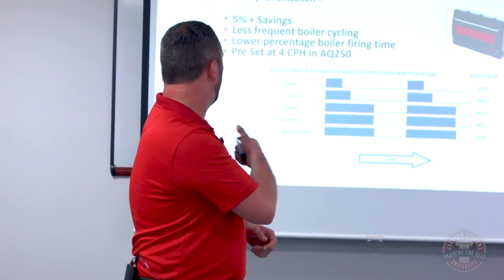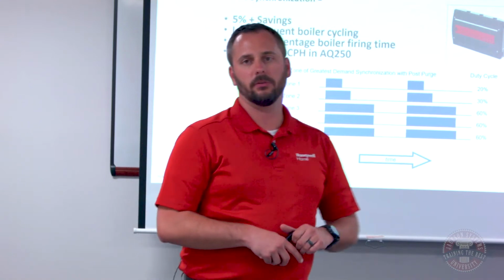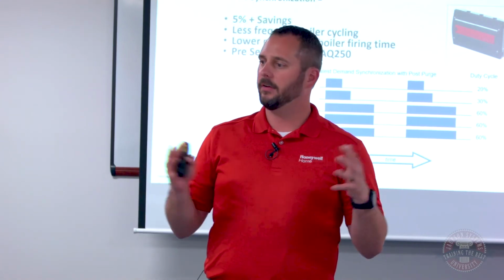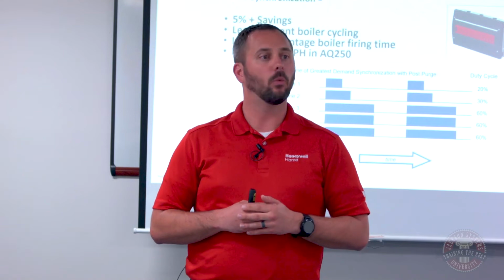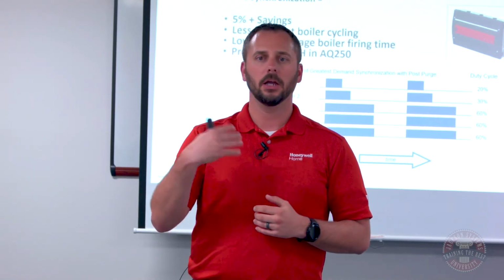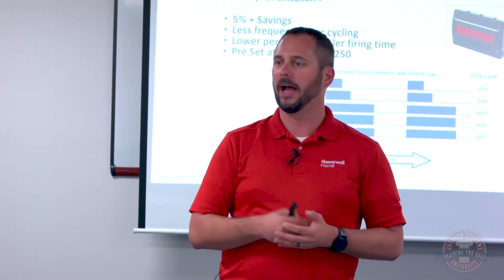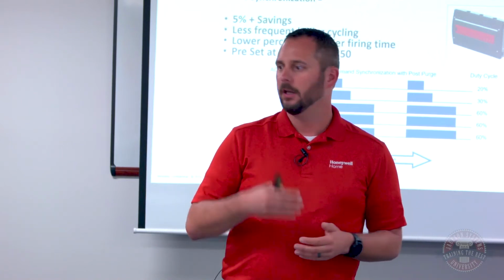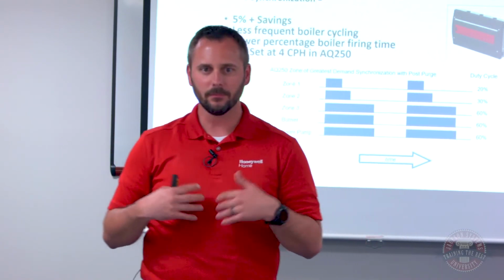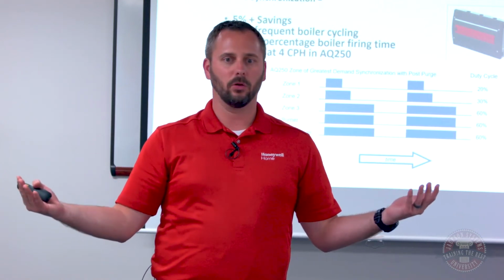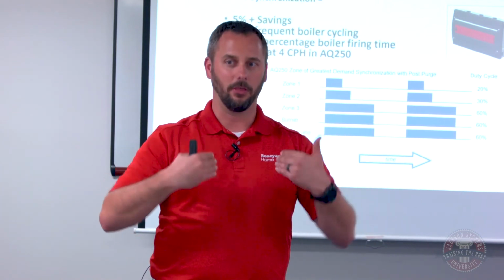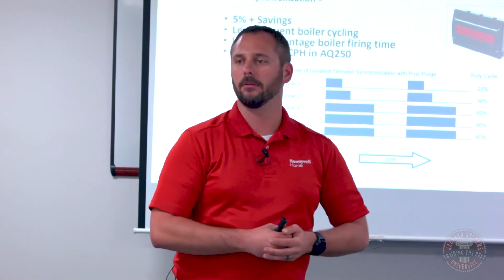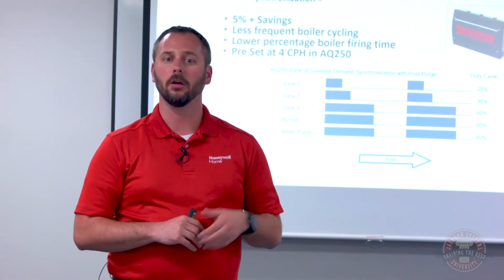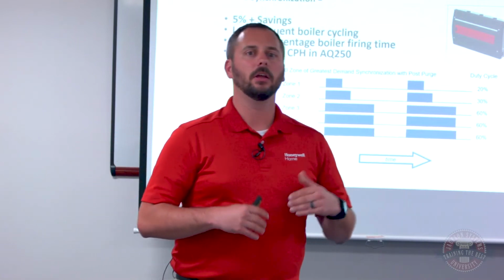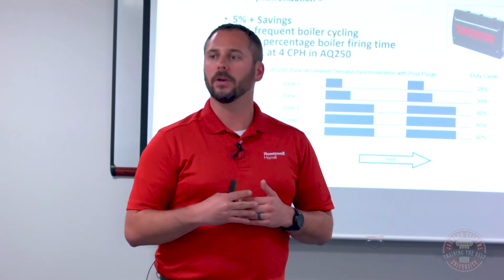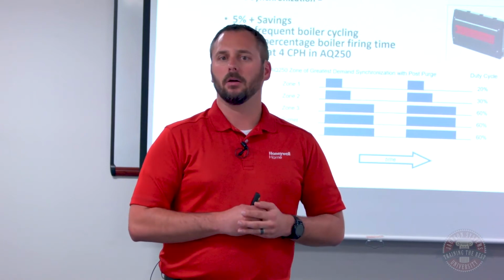So what we do in this example is the same scenario, but let's give it that same example of three of us sitting down, we're getting water. So I've finished mine, he comes back over, so he tops my glass off. While he's at the table, he fills yours up and yours up. And then he leaves. Well, now we're only waiting on the zone of greatest demand, or the thirstiest person, to come through and drink down to where we're going to need it again. So that's basically what this does, it puts a delay on the call for heat to the boiler based on what's happening in the system.